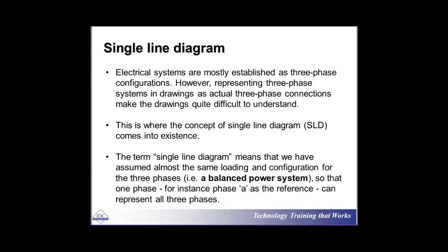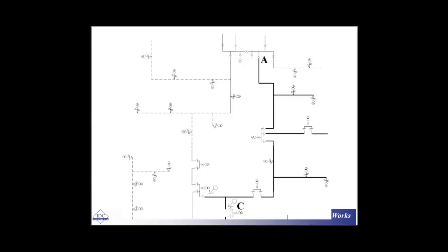This may not be a good practice on some occasions. So as a result, we prefer to show only one of the phases, which in many cases is phase A, the reference phase, which represents the rest of the system. We can do that as long as we have a balanced power system — meaning the loading on the three phases are almost equal, with almost the same current, same system voltage and power angle. If we have this, it is much more convenient to show the whole circuit by just one phase, which we call the single line diagram or SLD.